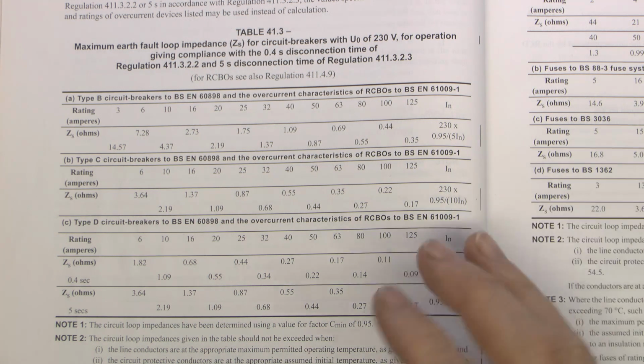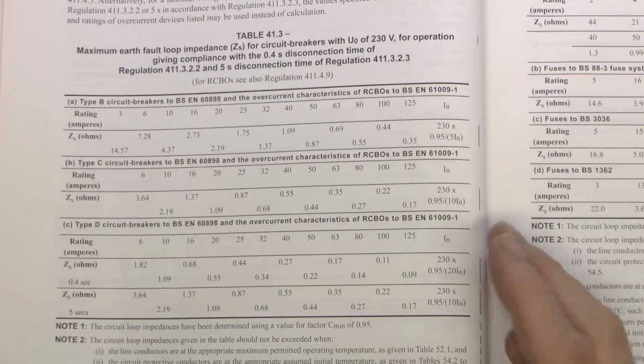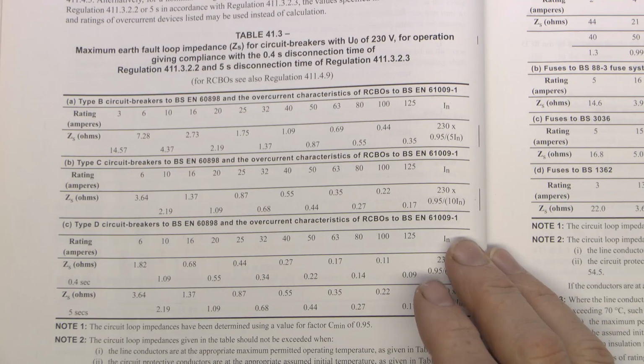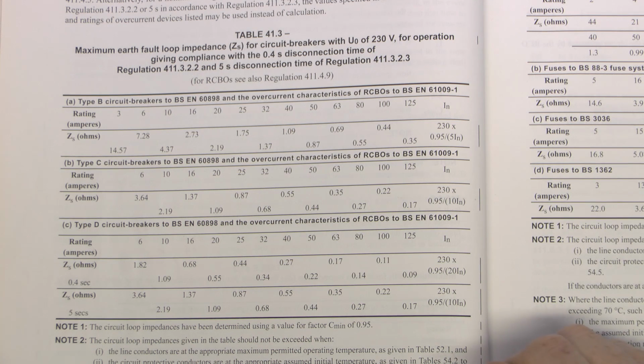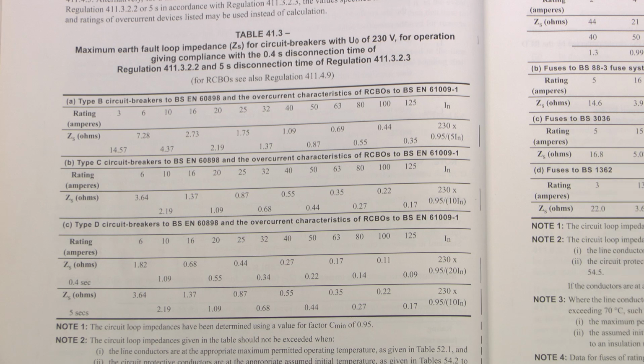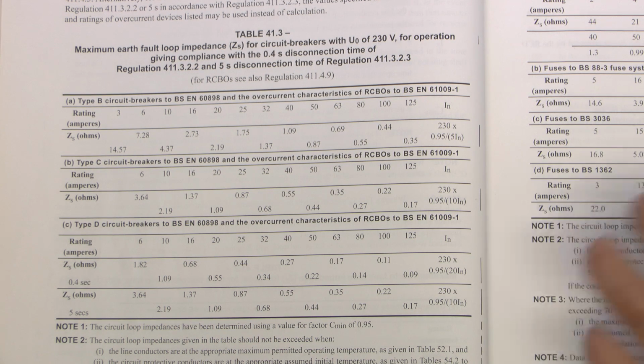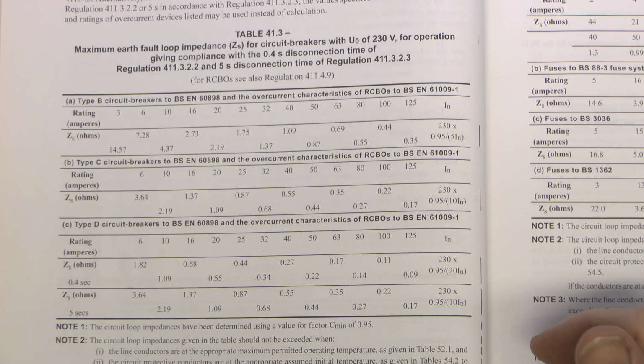And the reason for this is because the impedance of the circuit needs to be low enough to ensure that the thing will actually disconnect when a fault occurs, because bearing in mind, certainly on a type D, you could be looking at up to 20 times the rating of the circuit breaker to actually trip the thing. And of course, if you've got a fairly high impedance circuit, even shorting out between the two conductors may not actually produce a current of that required amount.